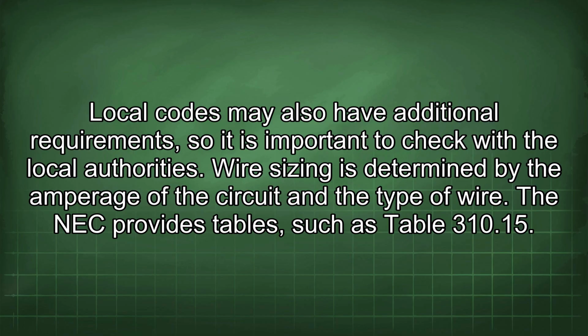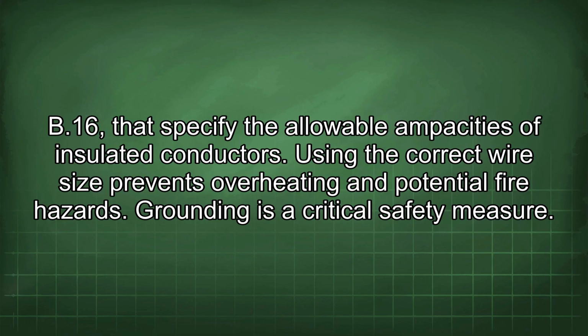Wire sizing is determined by the amperage of the circuit and the type of wire. The NEC provides tables, such as Table 310.15(B)(16), that specify the allowable ampacities of insulated conductors. Using the correct wire size prevents overheating and potential fire hazards.